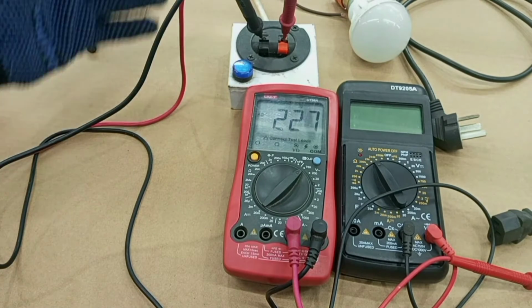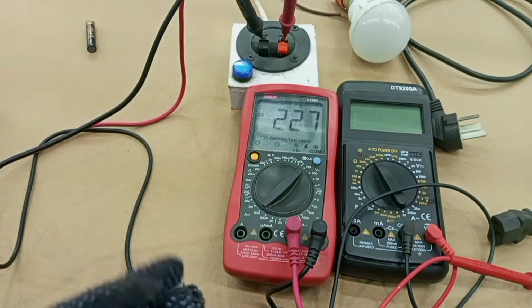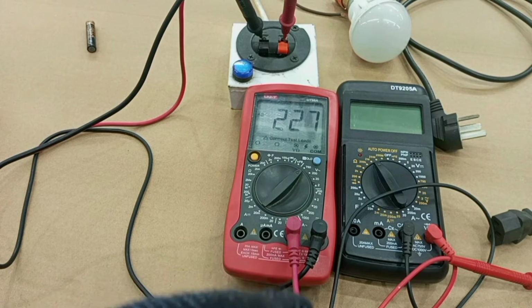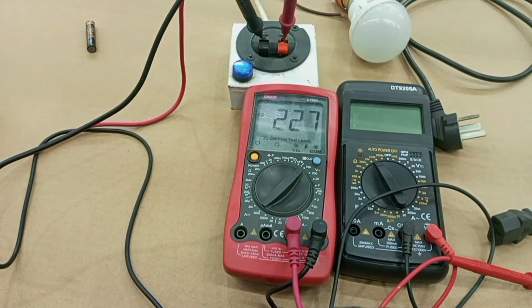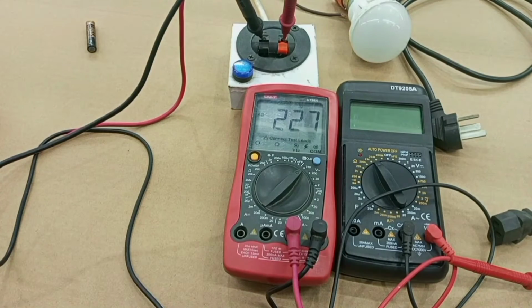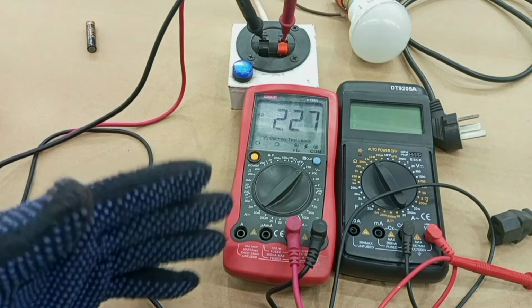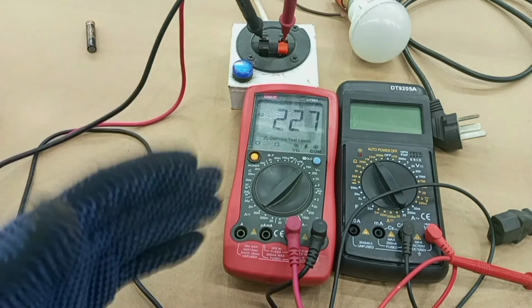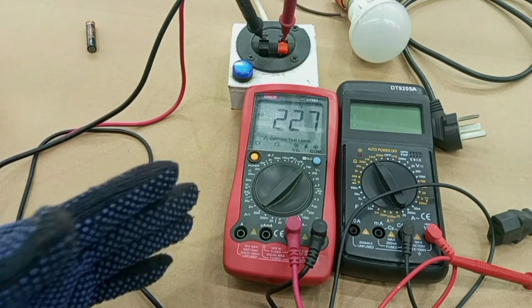Okay. And then you may want to check to be sure of the amount of voltage available at a socket or at a plug-in point so that you are sure there is enough voltage that can supply your appliance. And so in a 230 volt system, when you have your voltage around 227, you are very sure that if there is any problem that is causing an appliance not to work, that problem is actually not happening as a result of low voltage. So that is how to measure AC voltage.